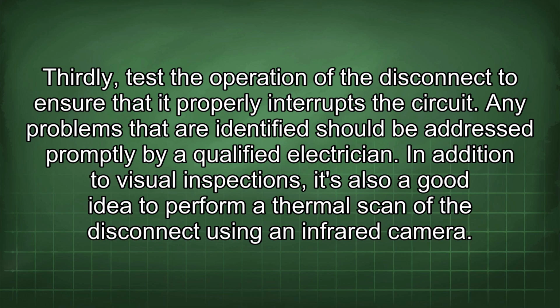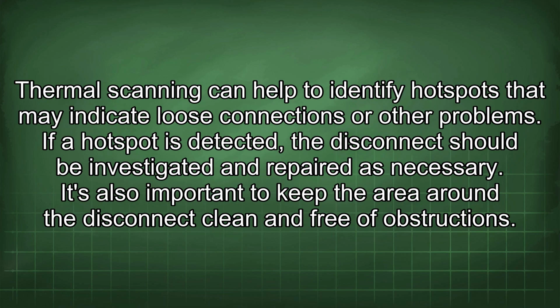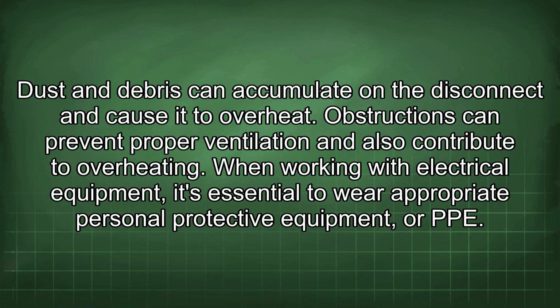In addition to visual inspections, it's also a good idea to perform a thermal scan of the disconnect using an infrared camera. Thermal scanning can help to identify hotspots that may indicate loose connections or other problems. If a hotspot is detected, the disconnect should be investigated and repaired as necessary. It's also important to keep the area around the disconnect clean and free of obstructions. Dust and debris can accumulate in the disconnect and cause it to overheat. Obstructions can prevent proper ventilation and also contribute to overheating.